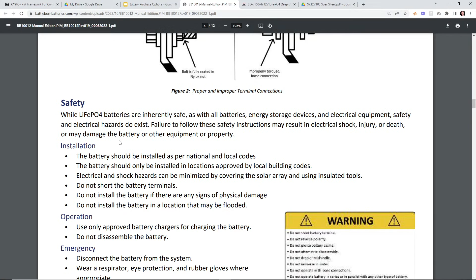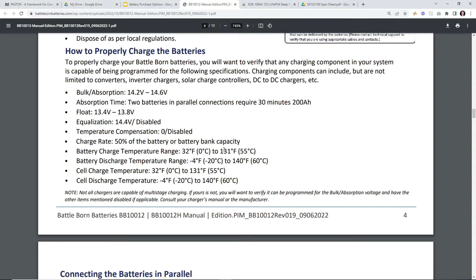So here we got 14.2 to 14.6. The SOK was 14.6. I mean, these are pretty much all going to be the same. Charge rate is 50% of the battery bank capacity, so 50% of the battery would be 50 amps. Charge temperature above freezing, discharge can go a little bit below that. That's quite a bit, but these higher numbers are about the same just for the chemistry.